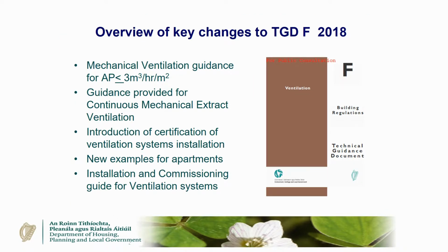Overview of key changes to TGDF. So we're doing TGDF in parallel with TGDL, they're both related. So I suppose what we're saying in TGDF is that where your air permeability is less than or equal to 3 metres cubed per hour per metre squared, TGDF advises that you should use mechanical ventilation. We've included guidance for continuous mechanical extract ventilation. That wasn't included in TGDF before.